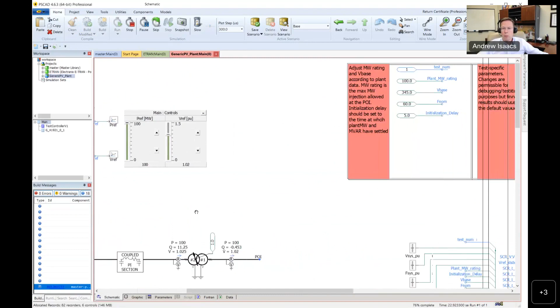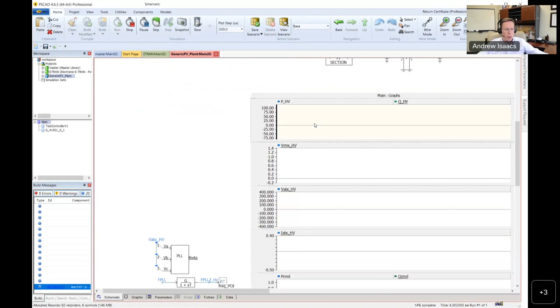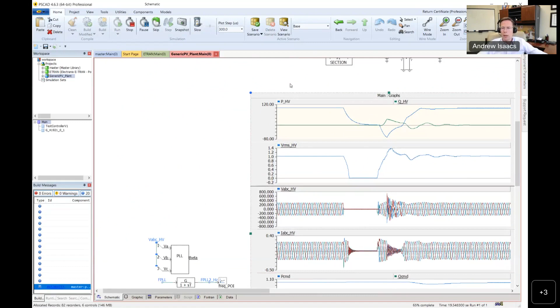You can say number 2 was a 3-line to ground fault at the POI at 100% power. Now we can watch this thing go through a fault, and see how the plant responded to that 3-line to ground fault.